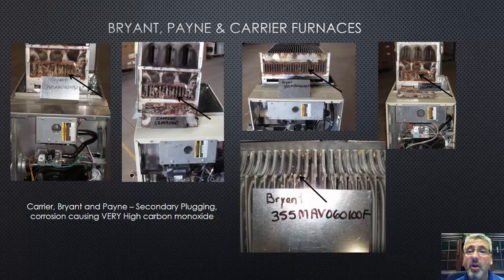So important. One other thing: anytime you change a heat exchanger, a secondary or primary of any type, you do those steps - gas pressure, delta T, all of that. You also check your vent termination, to make sure it's not recirculating outside.